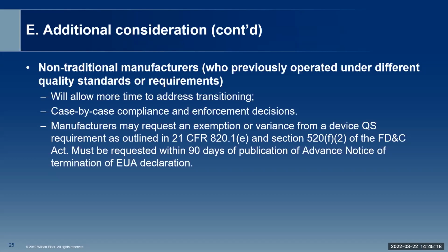So these non-traditional manufacturers, before the pandemic, were not subject to the heightened, stringent requirements for medical devices. So the FDA expects that these non-traditional players may take more time to address the transition. The FDA is willing to give them more time, and is willing to make compliance and enforcement decisions on a case-by-case basis with these non-traditional manufacturers. The FDA will also allow these manufacturers to request an exemption or variance from the quality standard requirements, the QS requirements, provided that such a request is made within 90 days from the publication of the advance notice.